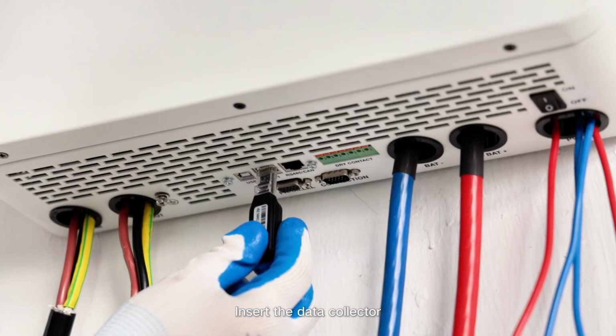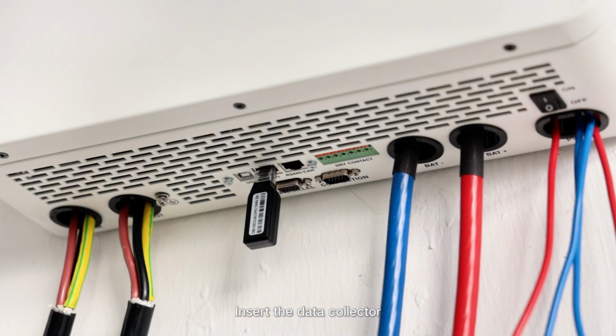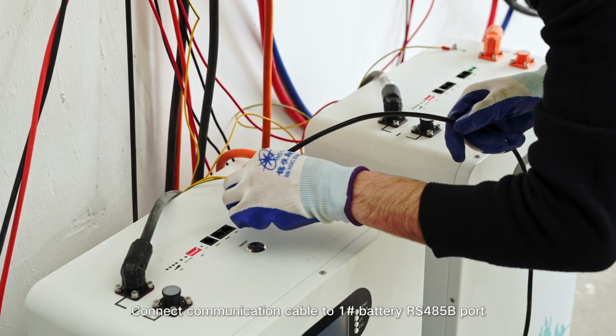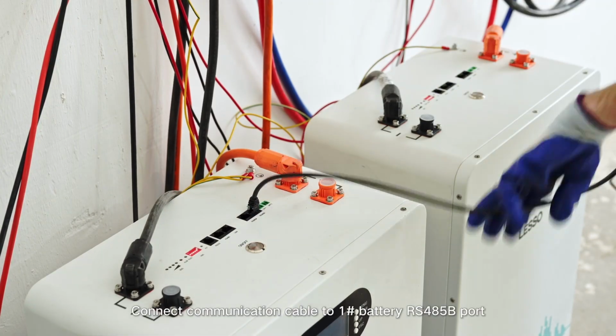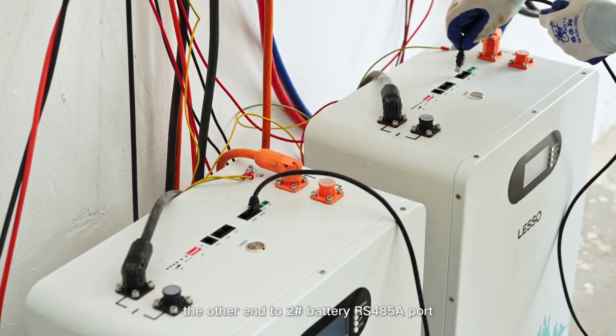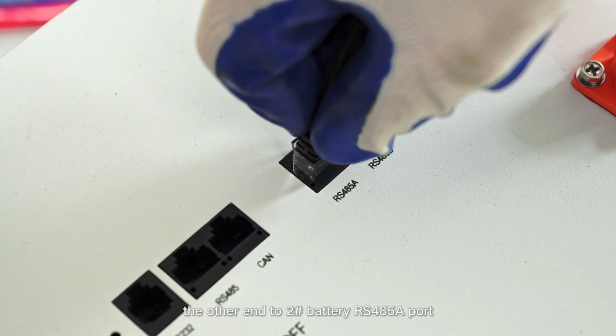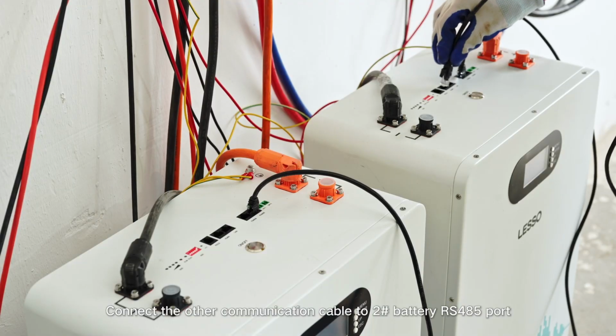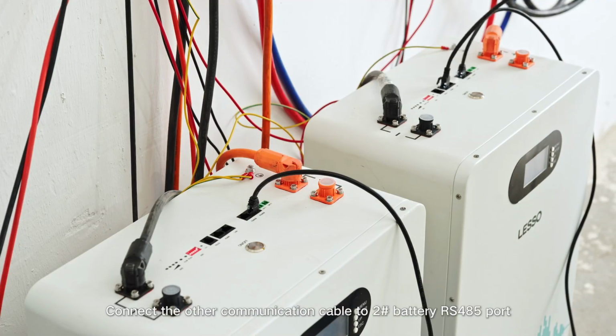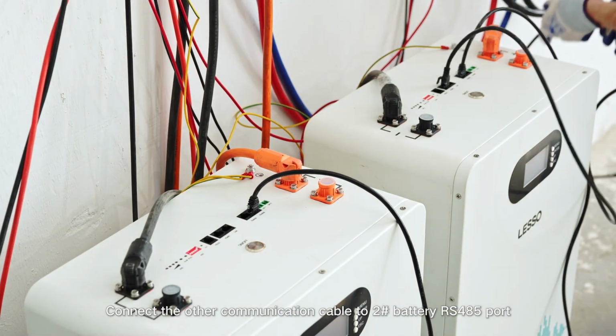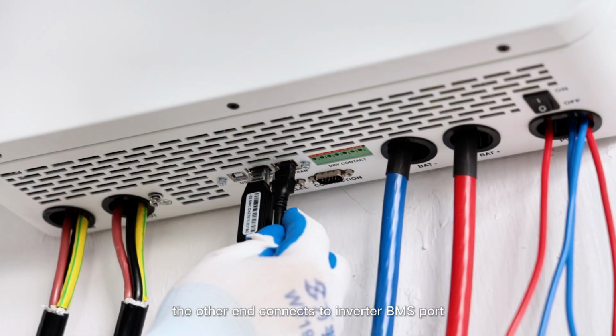Insert the data collector. Connect the communication cable to the 1-number battery RS485B port. The other end to the 2-number battery RS485A port. Connect the other communication cable to the 2-number battery RS485 port. The other end connects to the inverter BMS port.